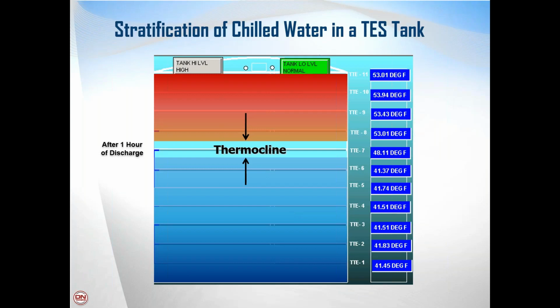And you can see how distinctly isolated they were from each other and stratified within that tank. The only temperature sensor, the one represented by sensor number 7, is the only one measuring anything other than 41 or 53 degrees. It's measuring 48 degrees, and that is in the region called the thermocline, which is the boundary layer between the supply and the return water temperatures. That thermocline is what the operators can watch as it slowly drops down through the tank when they are using the cold water. They're pulling that cold water out of the bottom of the tank and using it to cool the building, so as they're using it, that thermocline slowly drops down through the tank, and that's how they know how much cold water is still left in the tank.